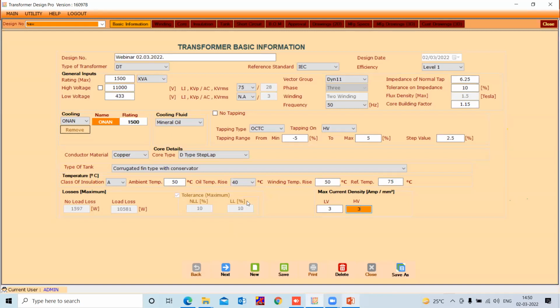Now, friends, those who have joined in the last 5 minutes, I would like to take a recap of what we have done, so that as we go further, it will not be difficult to follow where exactly we started. So let me reiterate. We have keyed in the design number. We chose the maximum rating, that's 1500 kVA here. The high voltage winding voltage is 11,000. The low voltage winding voltage has been written as 433. You can also see the ratings alongside it.